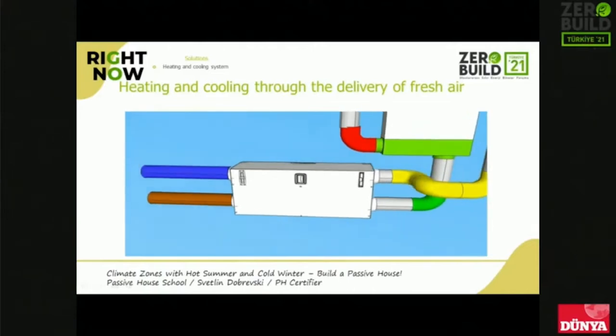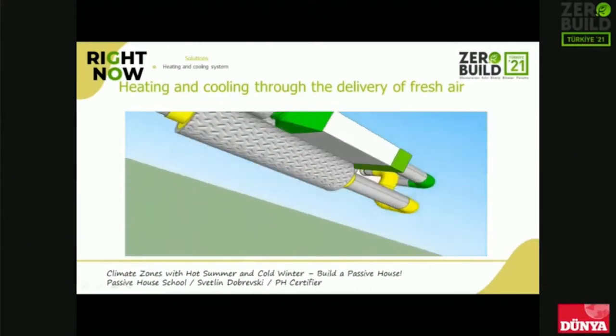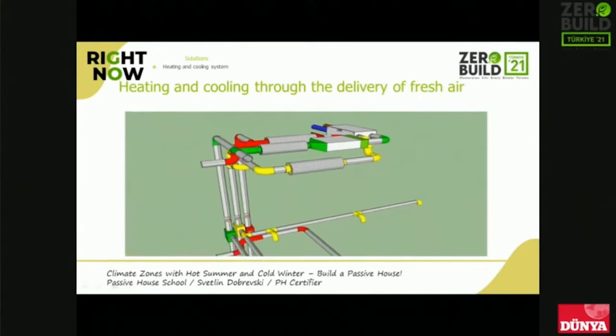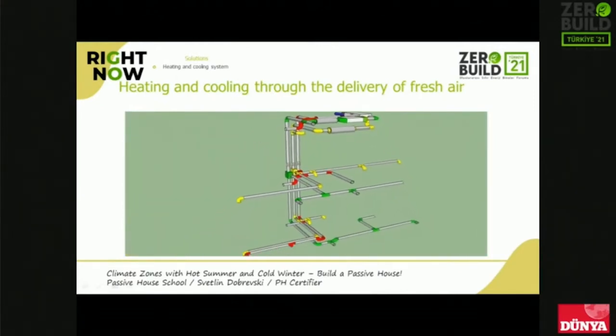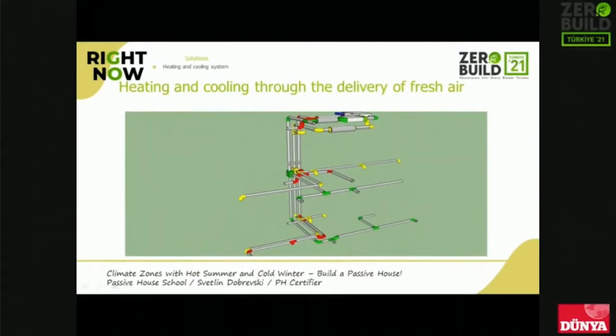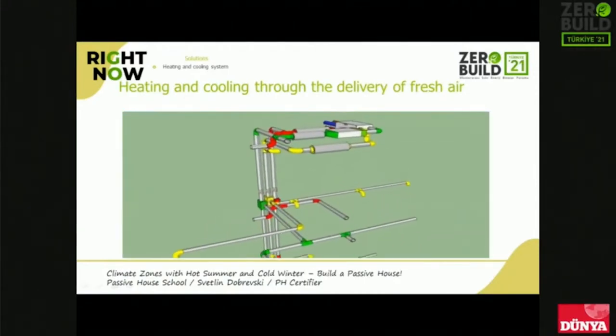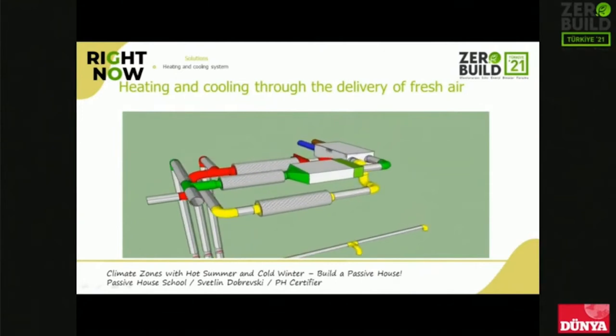building services equipment. Here you can see a standard mechanical ventilation system with heat recovery. The outside air, colored in blue, comes from the outside and passes through the heat recovery unit, and the fresh air, colored in green, goes into the living area. The extract air, colored in yellow, is taken from the service rooms and goes back into the heat recovery unit, where its heat is taken and transferred to the outside air. Everything is perfect, but with a cooling load of 12 watts per square meter, the air volume is not enough and can't transfer the power we need for heating and cooling.